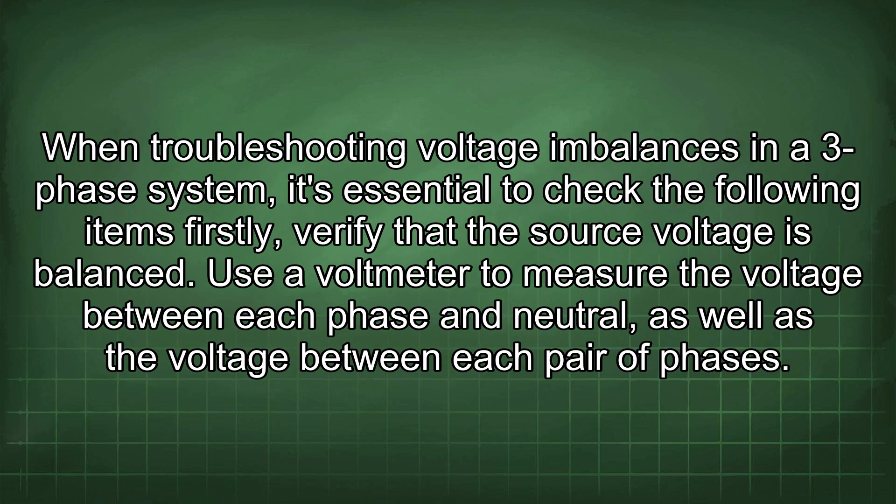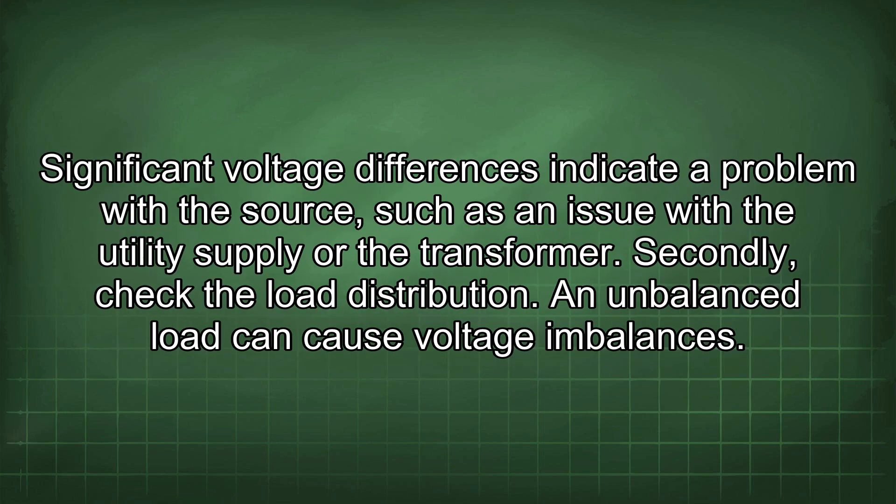When troubleshooting voltage imbalances in a 3-phase system, it's essential to check the following items. First, verify that the source voltage is balanced. Use a voltmeter to measure the voltage between each phase and neutral, as well as the voltage between each pair of phases. Significant voltage differences indicate a problem with the source, such as an issue with the utility supply or the transformer.